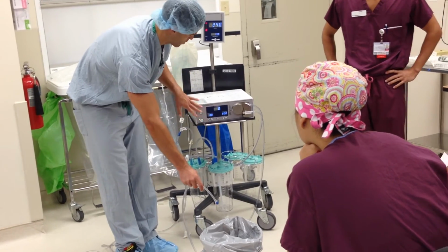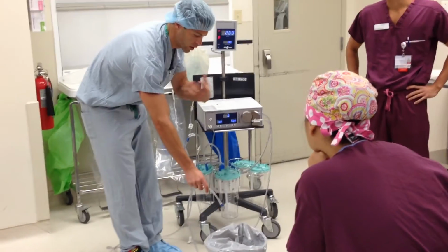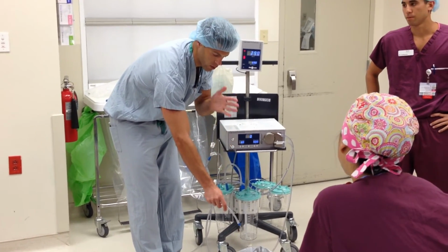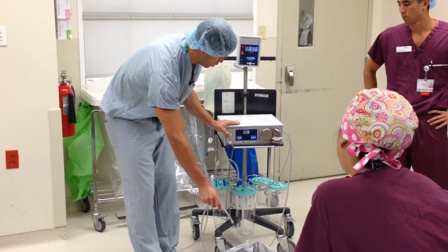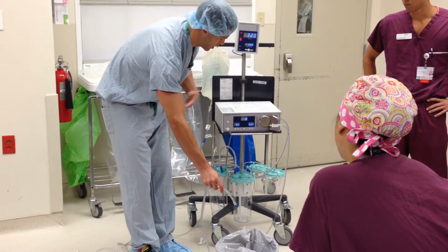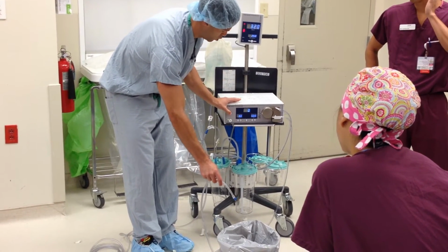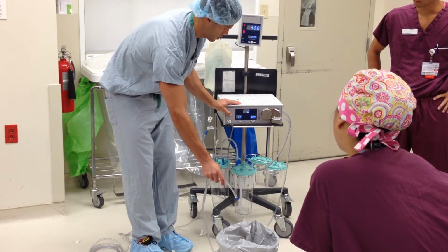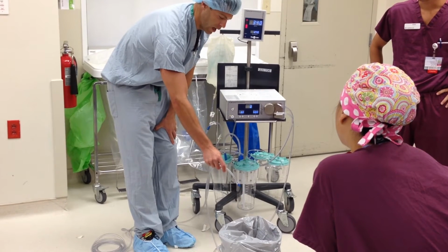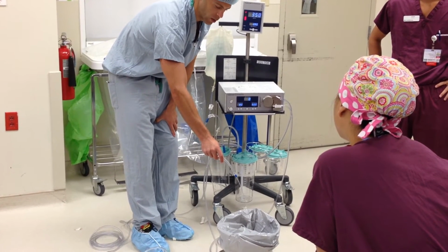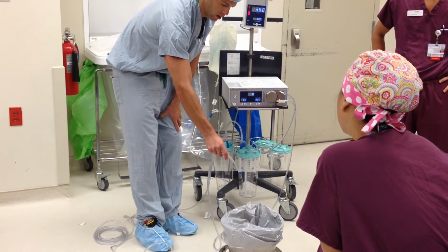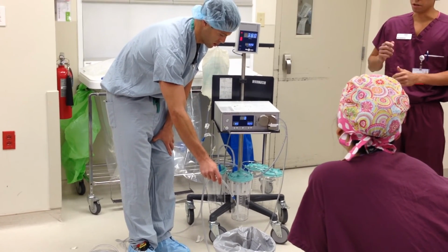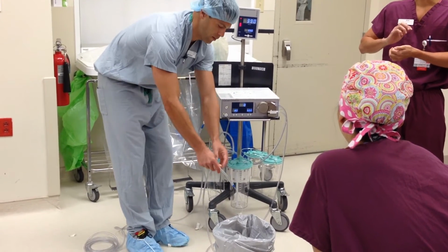So we started the pump to prime it. Now, in order to go through the equipment detection, so the pump knows the spacing it has to pump water through with the sheath and the scope, you stop the pump. And then in order to get into the equipment detection, you hold this stop in until it beeps, like that, and then you let it go. And now it's going to be a 12-second period where it goes through the equipment detection process.